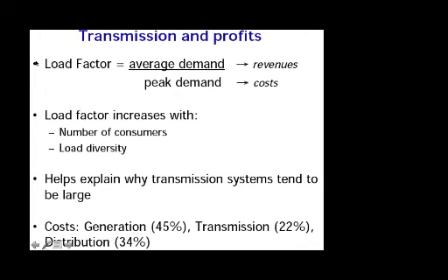The load factor is very important in determining the cost of electricity. Your peak demand determines how much you have to pay to build a facility, because you need enough generation capability to meet your peak demand. Your average demand is the amount of electricity you sell, which is your revenue. So we would like this ratio to be as big as possible, as close to 1 as possible.